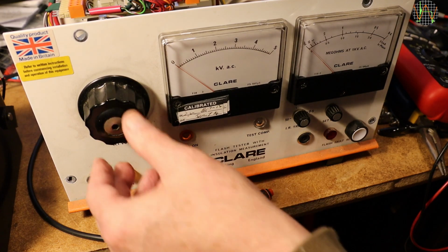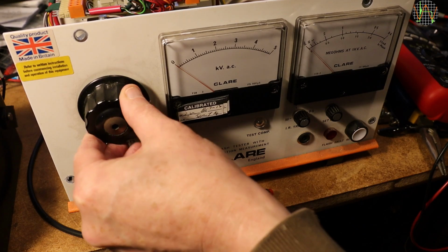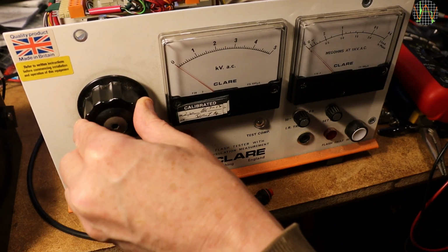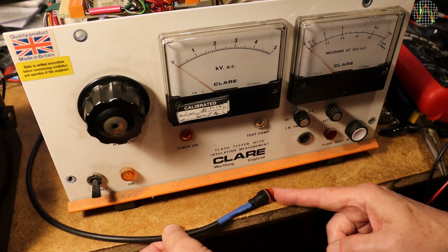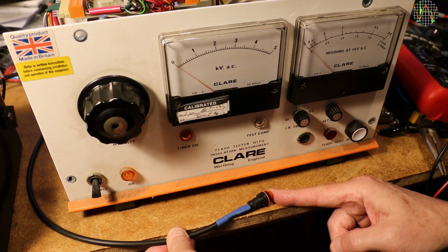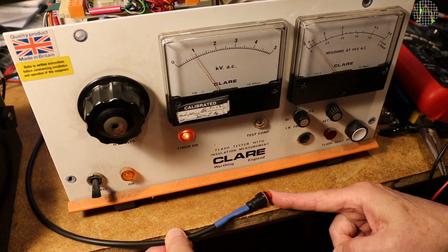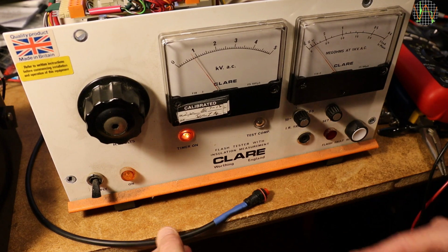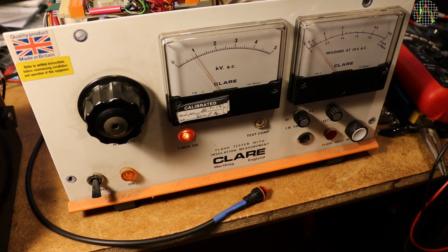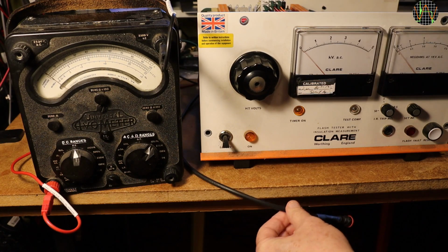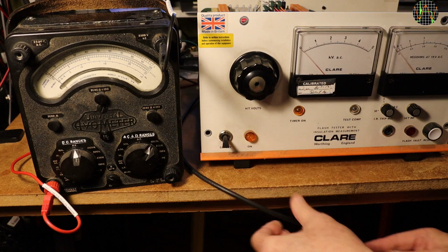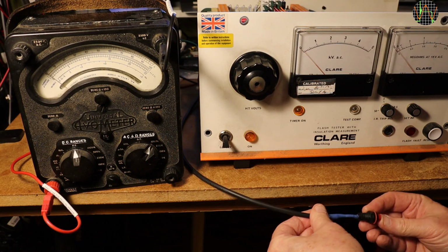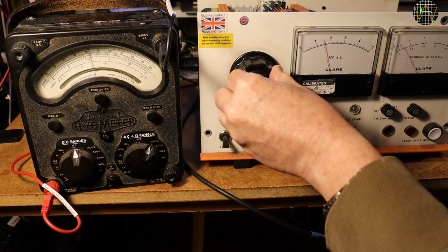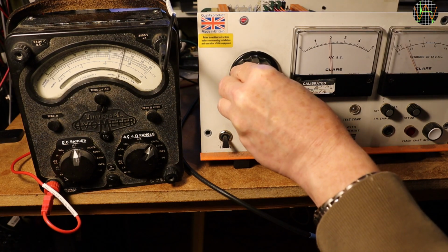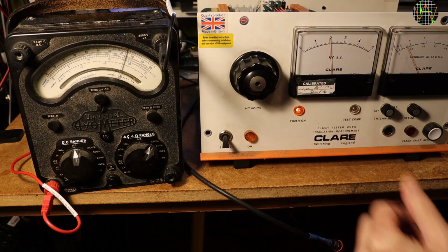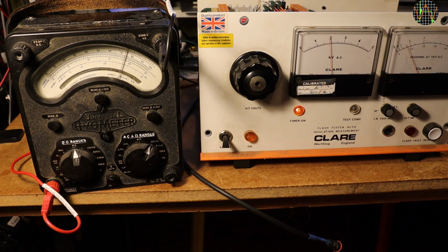Now the crucial part, do I get any output voltage? I set the voltage very low. Yes, as soon as the timer is running, we get nearly 1 kilovolt and also some current on the meter on the right. Success, the unit is working. It is a bit annoying that one has to start the timer to set the output voltage. But anyway, the AVO shows there is a high voltage coming from the output. The camera angle is slightly to the side, but the output is indeed a little below 2000 volts, so the AVO and the built-in meter are in agreement.